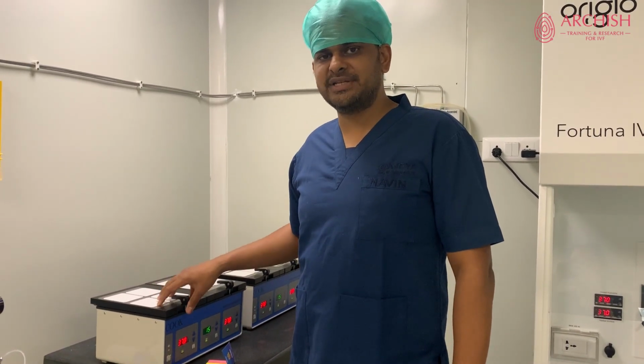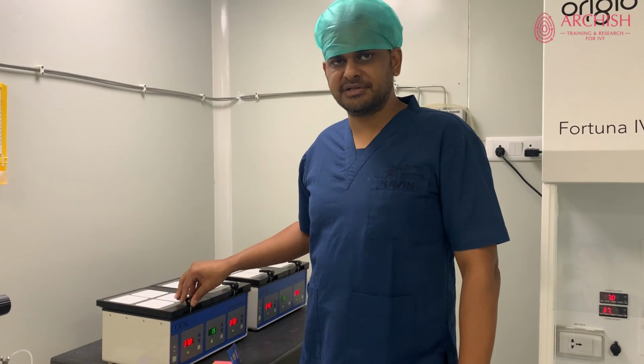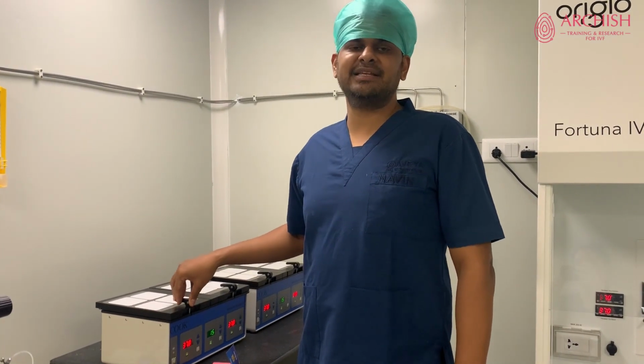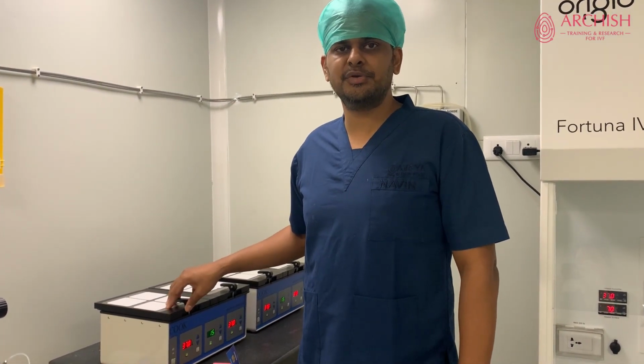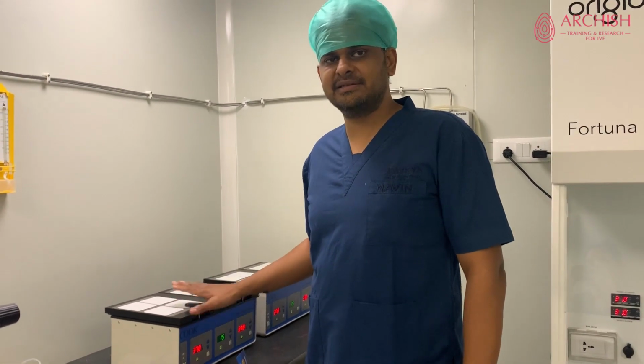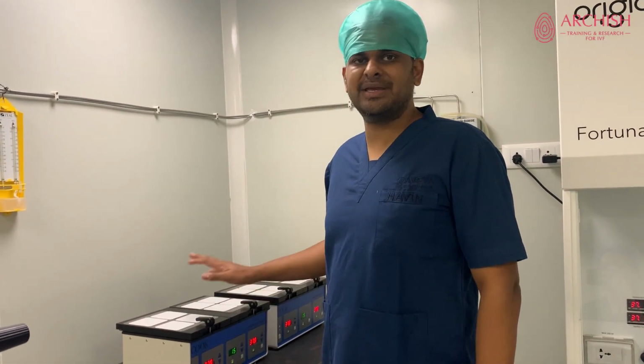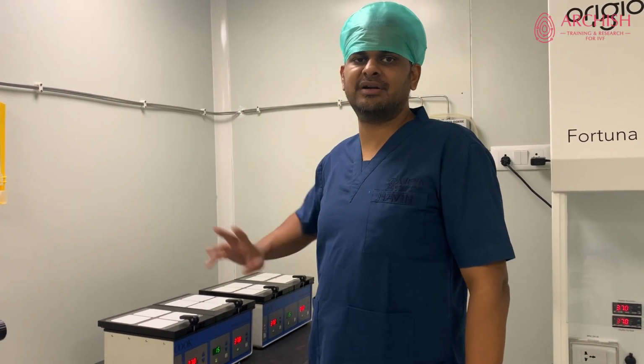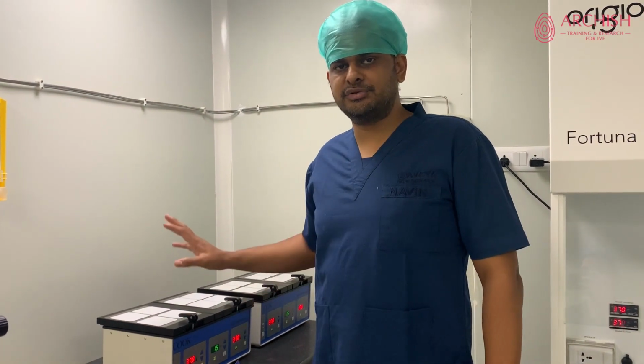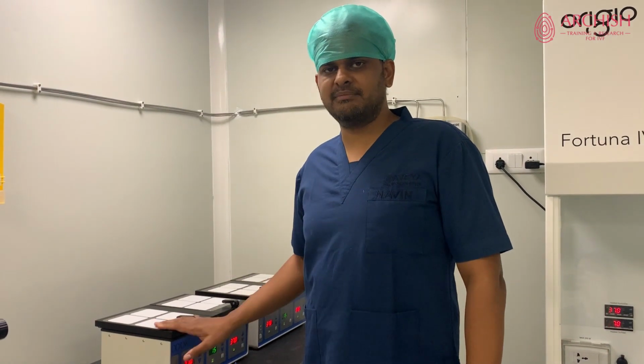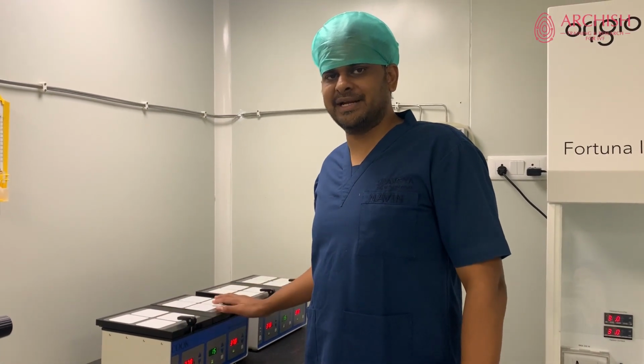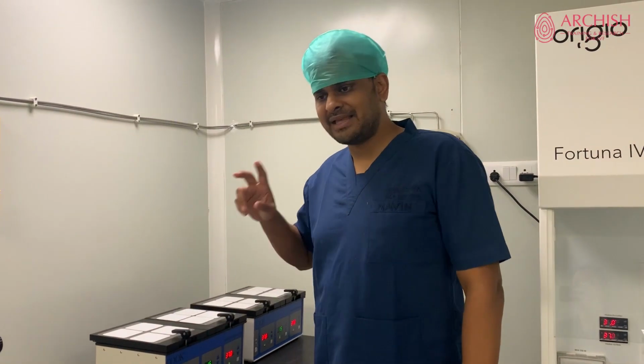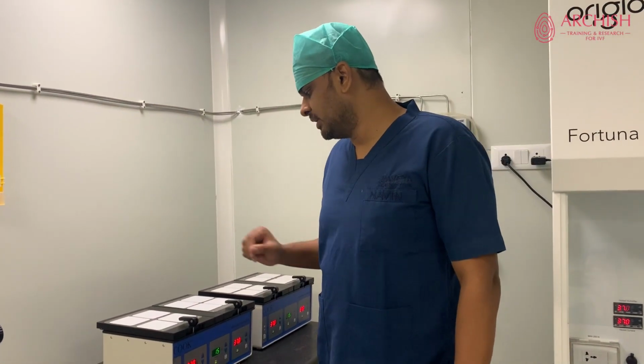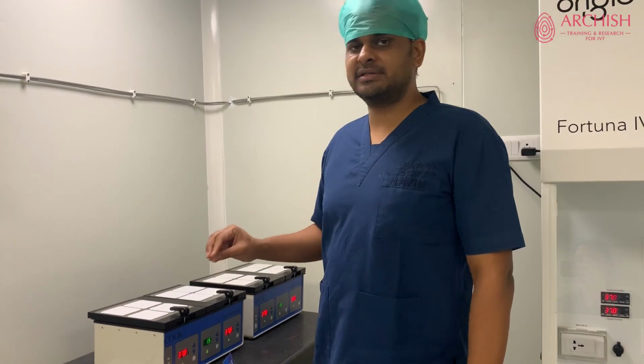So we need to check for that along with the temperature. When you come to testing QA/QC parameters inside the incubator, you have to insert two probes inside any of these chambers. You can keep alternating these chambers every day - it's not necessary to take the QAQC reading for both chambers. For example, if today is Monday, you check the left side; Tuesday you check the right side.